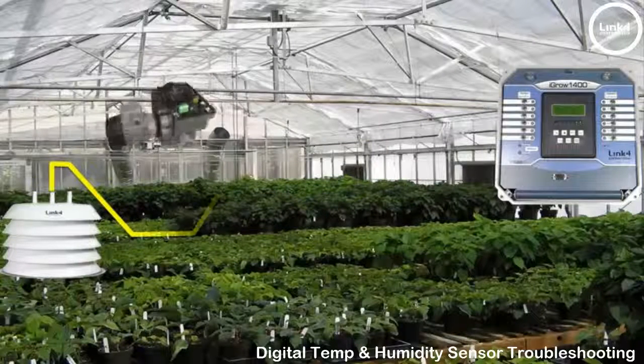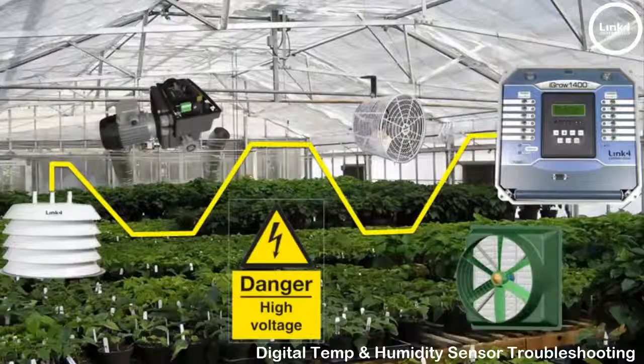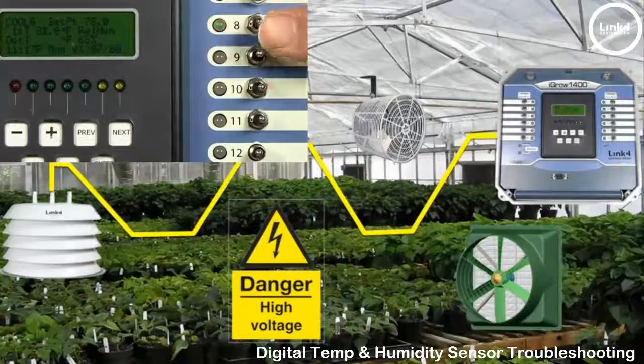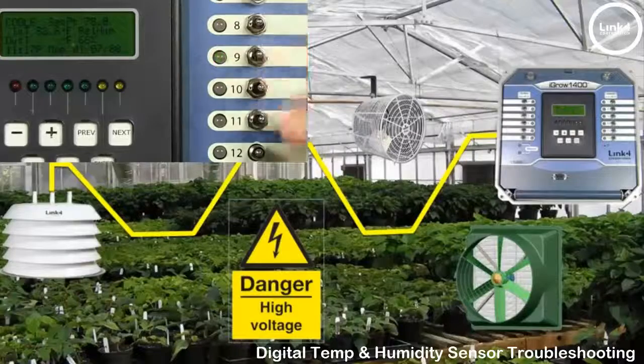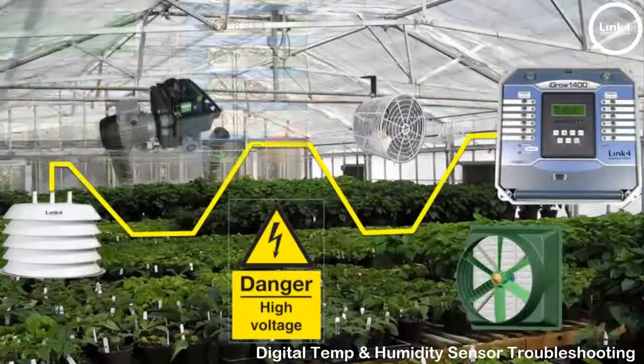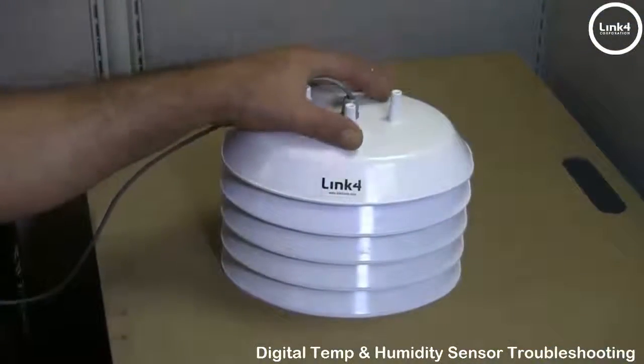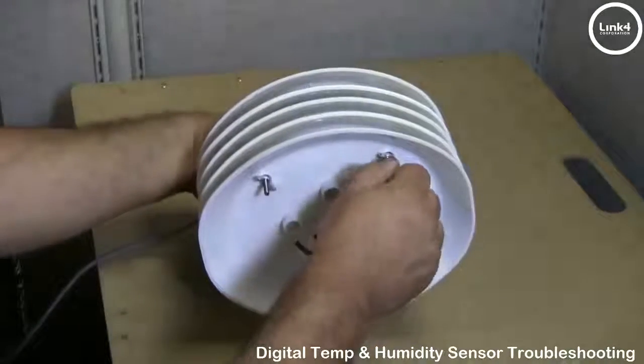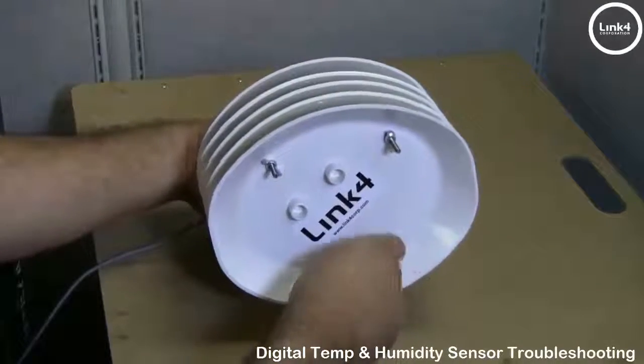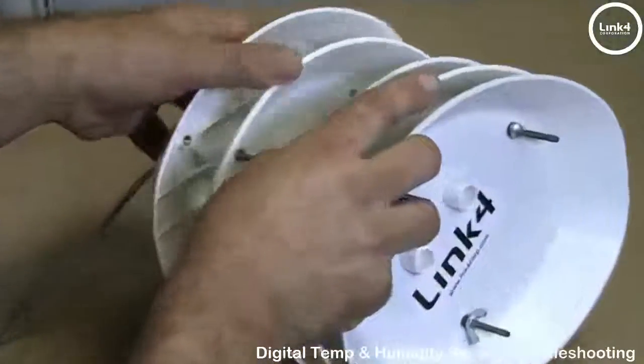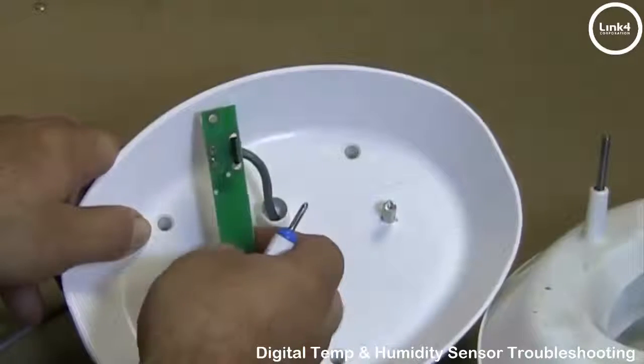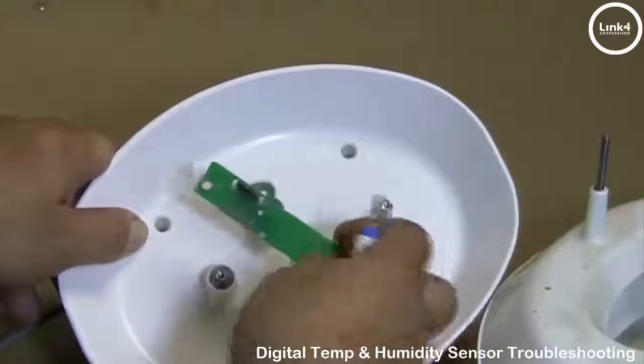You also want to make sure that the line that's going from the controller to the sensor is clear from interference sources such as voltage, motors, inverters, etc. You may also want to try toggling on and off the switches on the front panel one at a time to see if the sensor stabilizes when doing so. Now, at the sensor itself, you want to disassemble the radiation shield that houses the sensor and examine the PCB board that's inside to see if there's any corrosion, moisture, or contamination buildup. If silicone is not present covering the sensor cable to the PCB soldering points, check at that location for oxidation and use a fine metal brush to gently remove it, then put it all back together again.